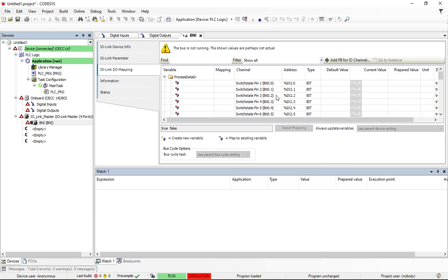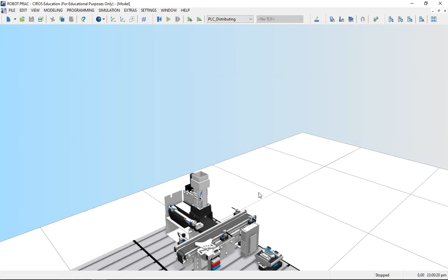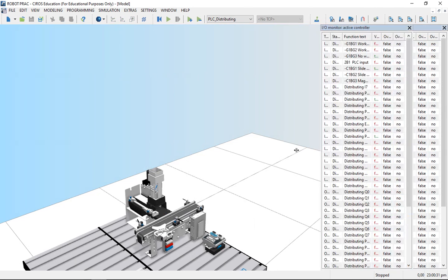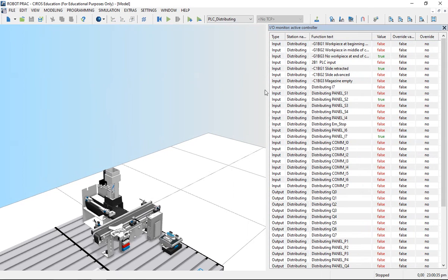So we shouldn't act surprised. We know that we're dealing with these outputs here, the 2. So now on the output 0, we can change this value, and it should affect the Q0 over here. So to see that, let's rather come here, show monitor there. Let's monitor it, and let's expand. You see there's one thing that we don't need. The station name we don't really need, because we can see that these are the outputs that we're trying to control. All right, so let's just press play.